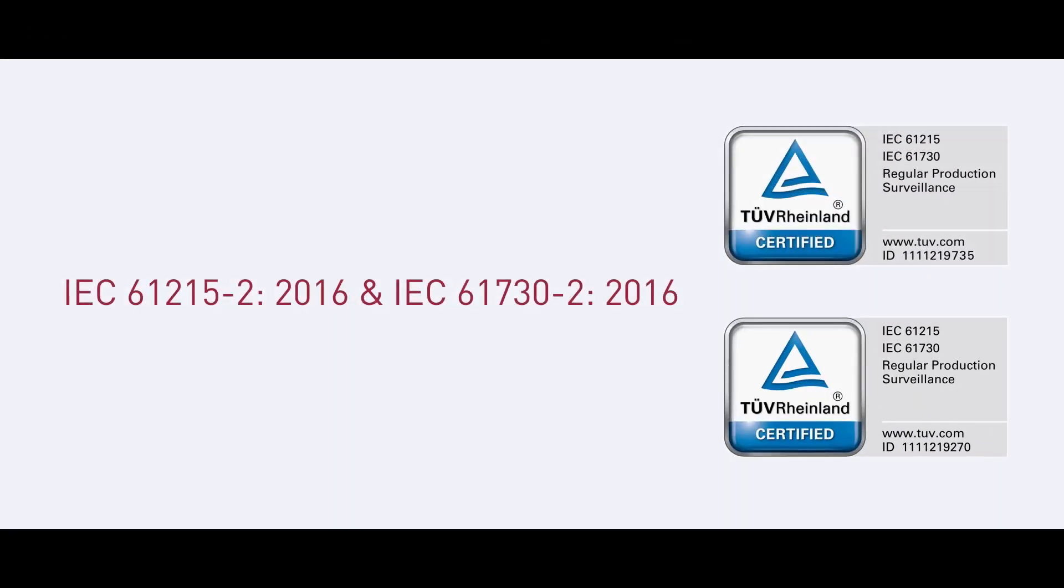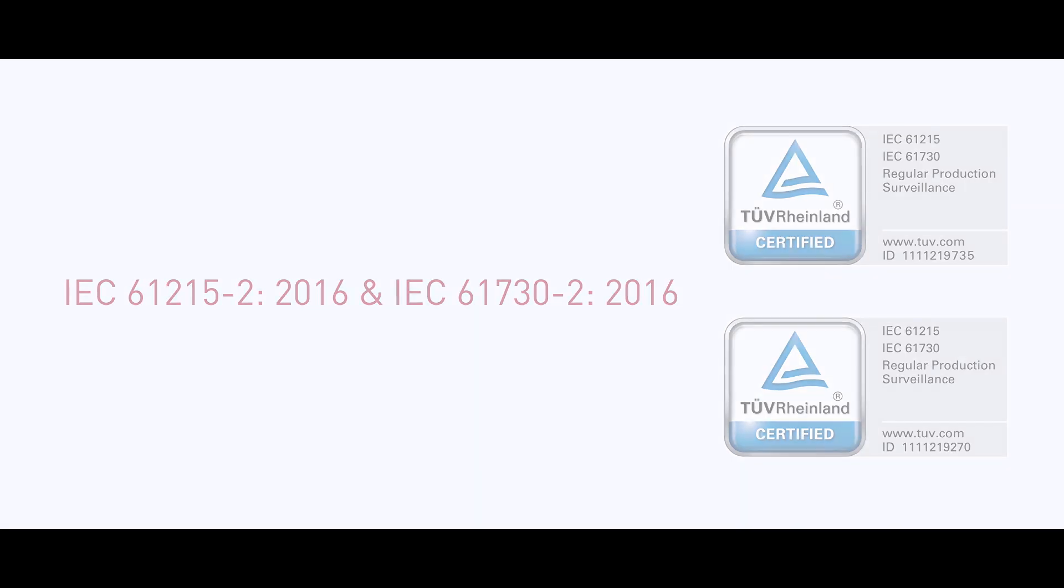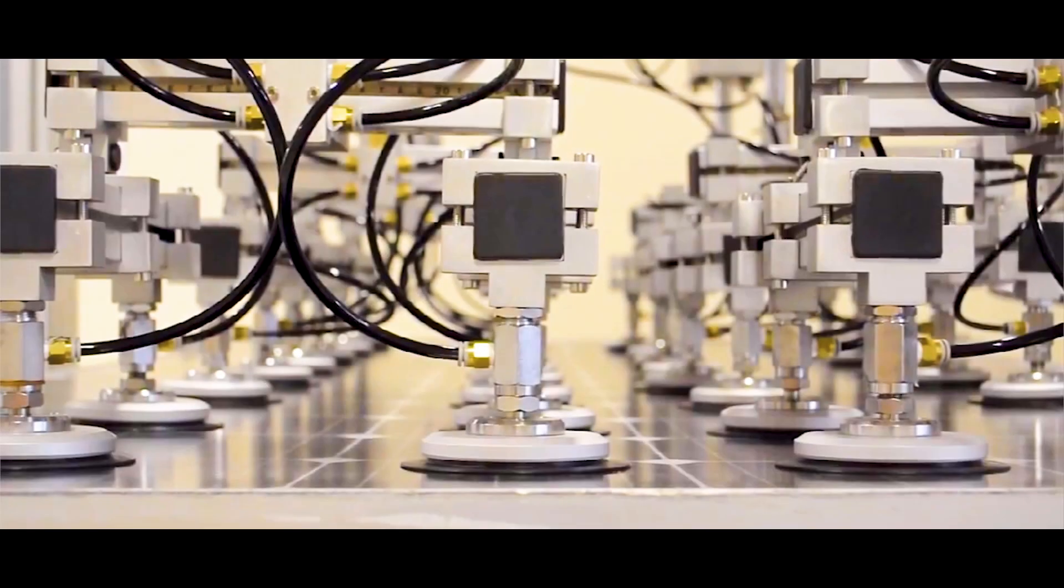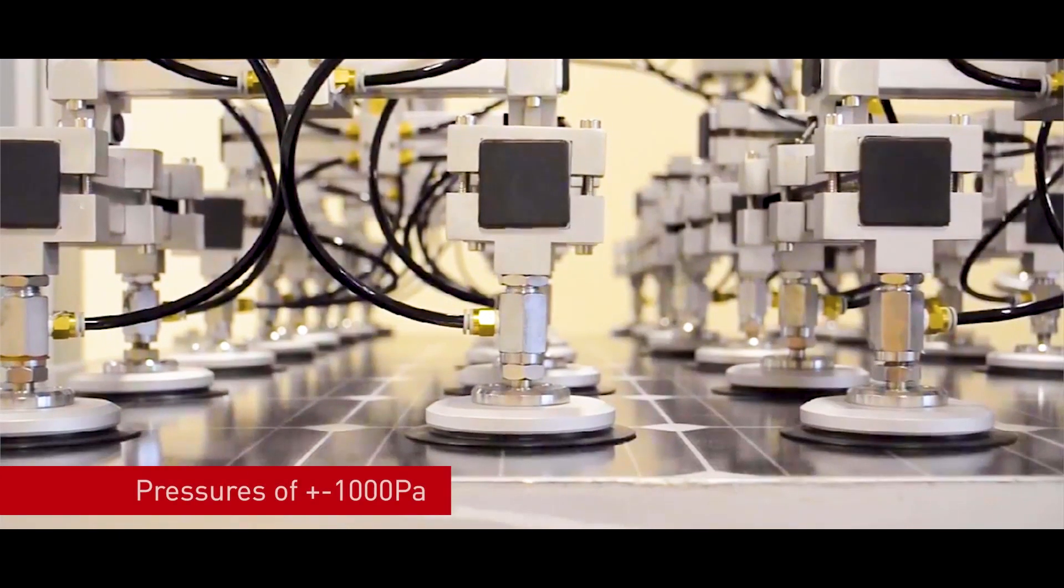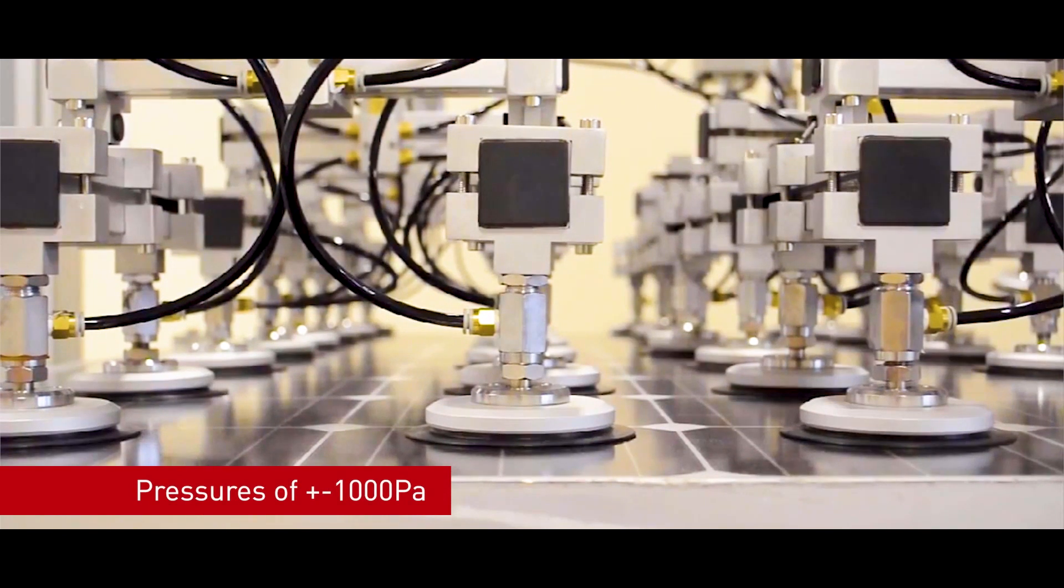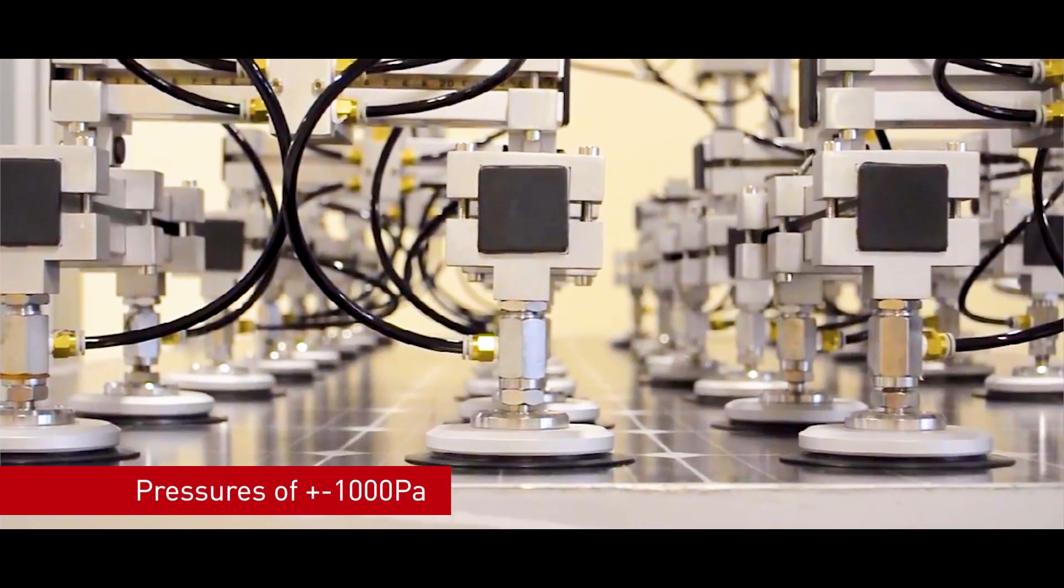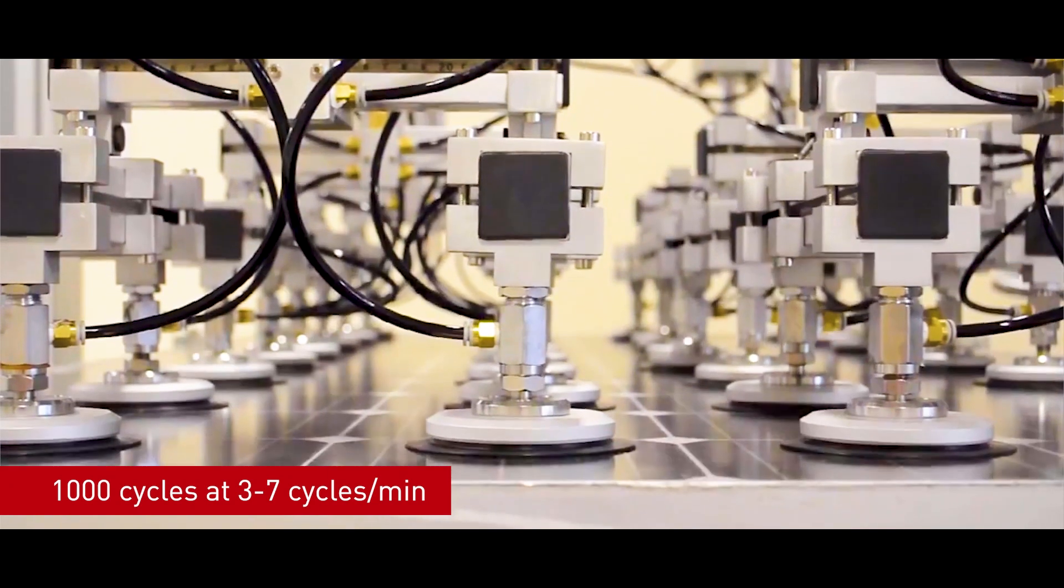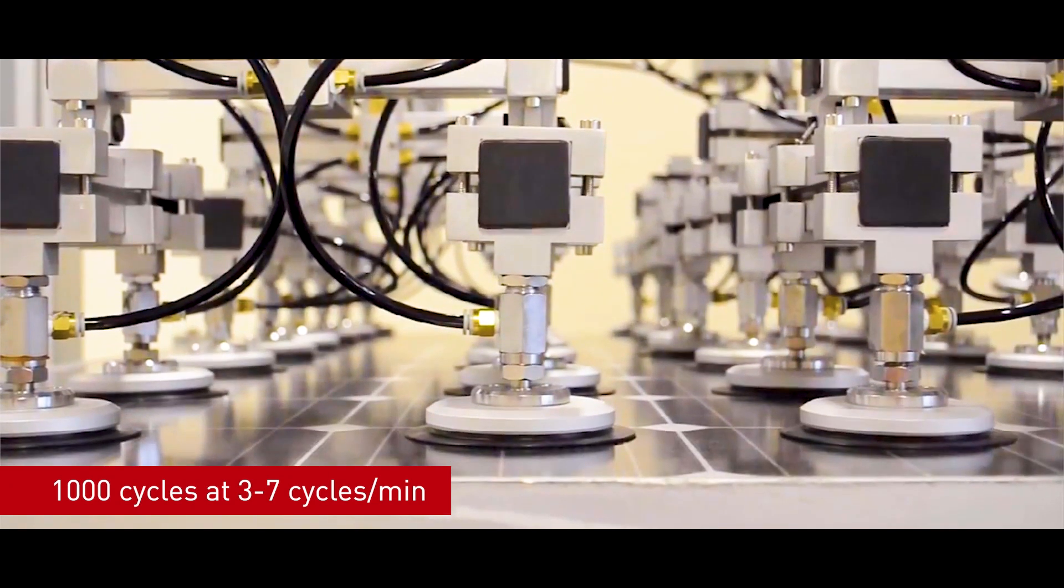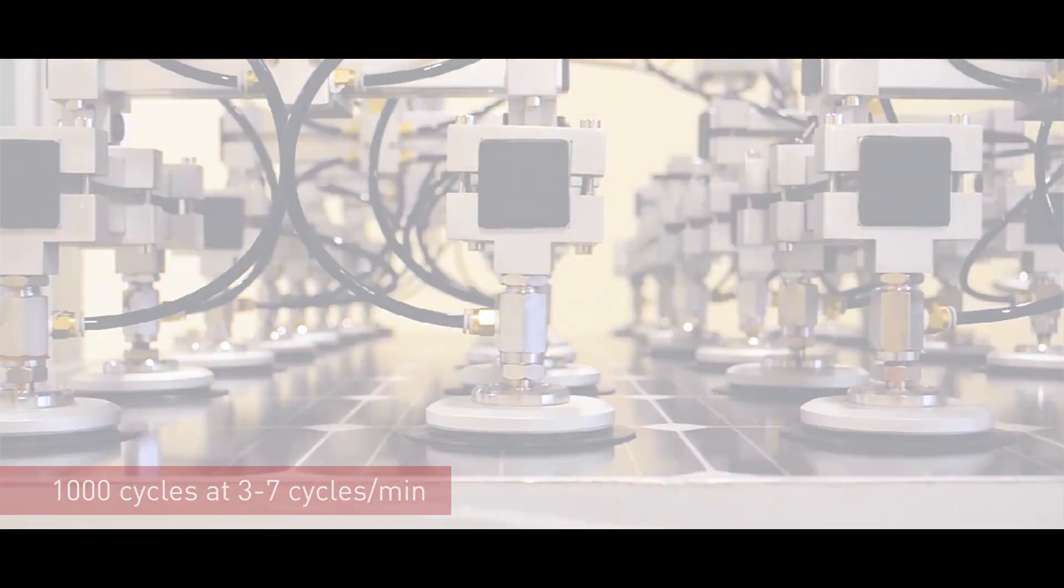The solar photovoltaic modules are IEC 2016 certified. Further, IEC TS 62782 ensures performance against cyclic mechanical load by testing at pressures of plus or minus 1000 Pascal for 1000 cycles at 3 to 7 cycles per minute.